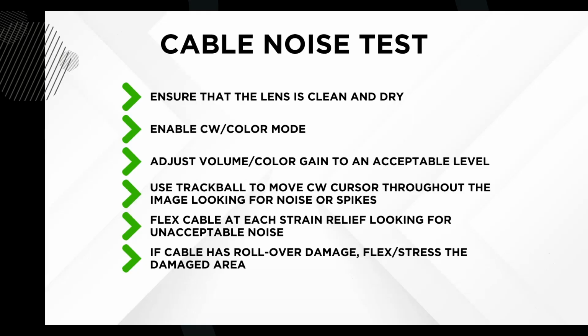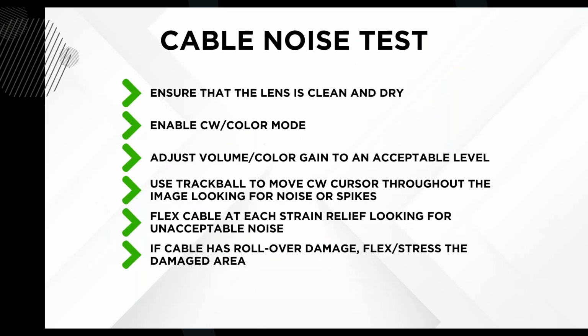All right, the final test that we have on here is the cable noise test. For a cable noise test, we want to ensure that the lens is clean and dry. You enable continuous wave or color mode on the system and adjust the volume and the color gain to an acceptable level. You use the trackball to move the continuous wave cursor throughout the image, looking for noise or spikes. Flex the cable at the strain relief, looking for unacceptable noise, and check the cable to make sure it doesn't have any rollover damage, flex or stress in the damaged areas. Basically, we're talking about the cable.